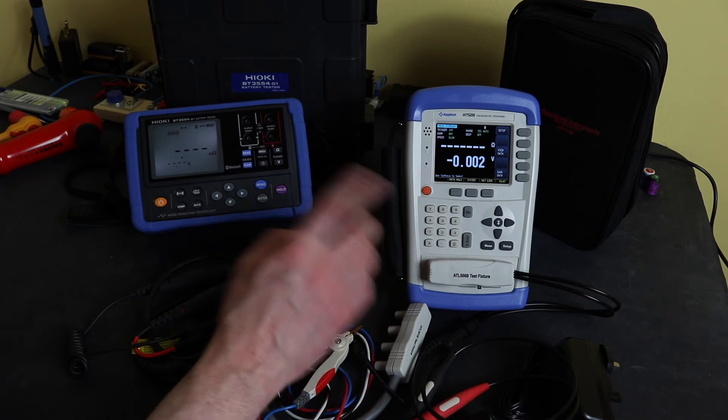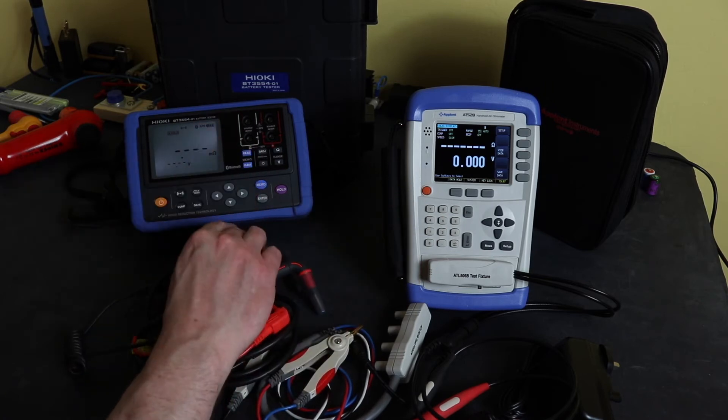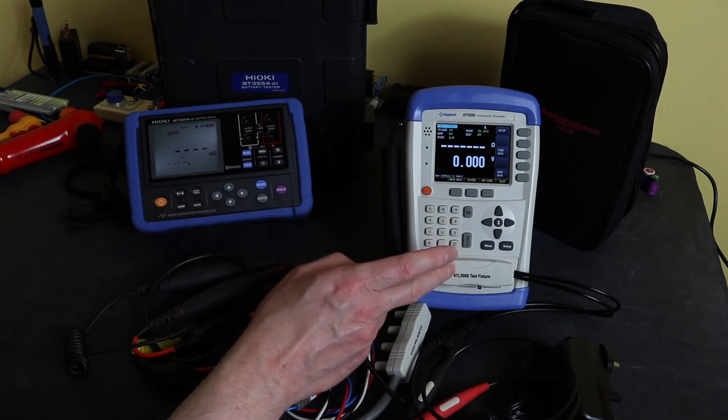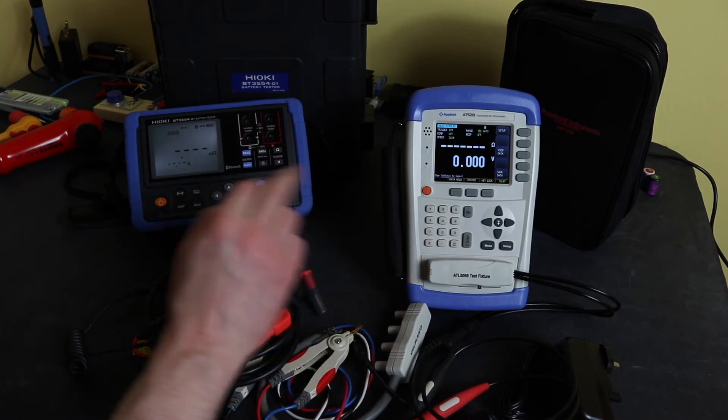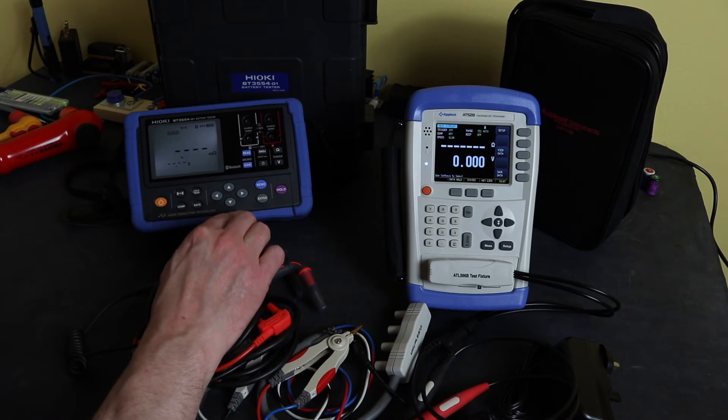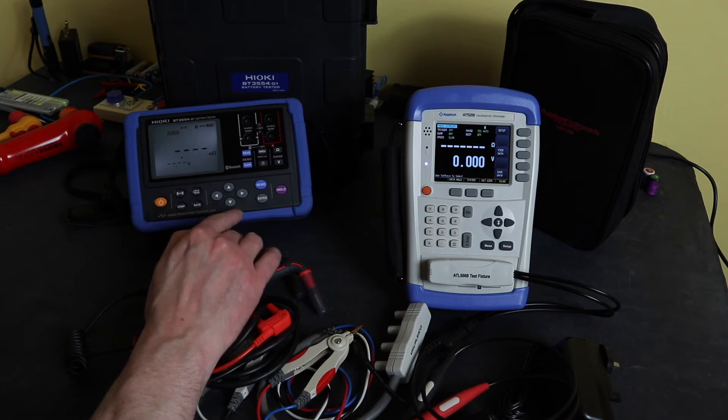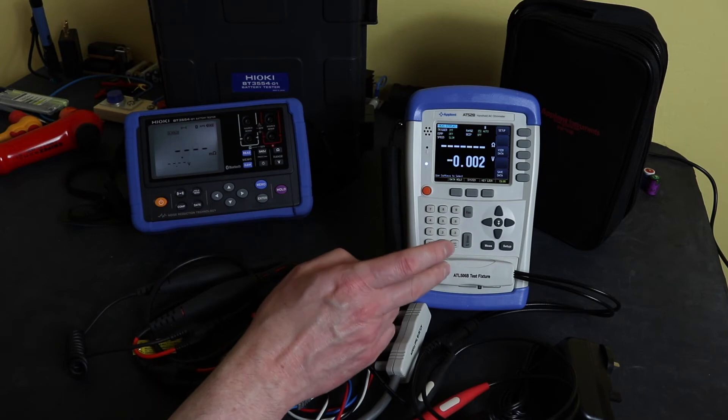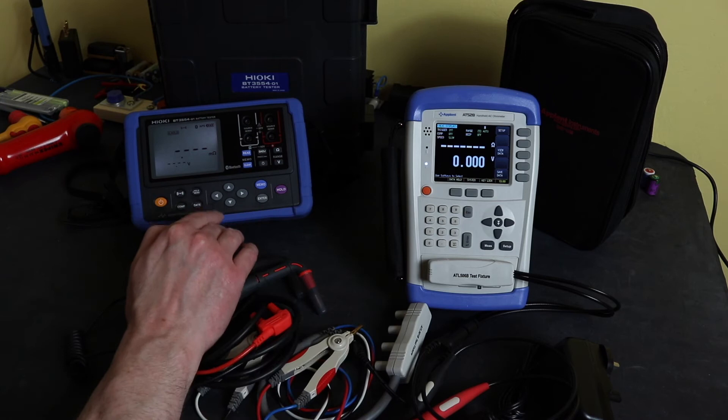Both of these units have memory on them. This does 6,000 records, this will only do 2,000 records. In comparison to how that works on this, this splits the memory up into 12 slots so I can do 12 different sets of batteries and test them and save them independently, whereas this is just a basic one set of records 1 to 2,000. So I kind of prefer the way the memory is set up on this - it's much more user friendly and versatile for my kind of work.